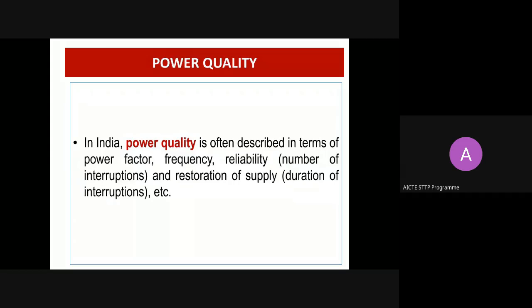It means the utility has to provide power continuously without much interruption. If there is an interruption, it should be within a limited level. The number of interruptions is also most important. Again, how quickly we are restoring. The interruption may be for 1 or 2 days, but if you are restoring after a long duration, it affects the performance of the other industries. So these are the major factors which coin the word power quality.